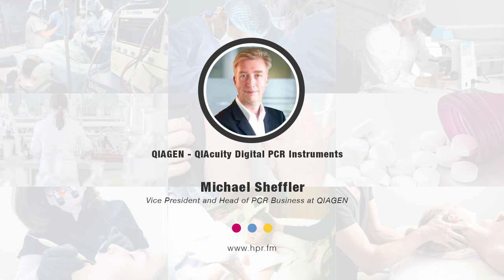When it comes to QIAcuity, does one size fit all? Are there different versions, different working techniques? That's an interesting question. QIAcuity comes with three different main variants. You can either load one plate, four plates, or eight plates — similar to the SBS format, the standard laboratory plates — into the system. Depending on this, you also have certain walk-away times, which is what instrumentation and automation are after. So it helps you achieve throughput, whether you need a quick, fast turnaround like in an academic setting, or you're in an industrial setting like biopharma, where you have several hundreds or even thousands of samples to process.